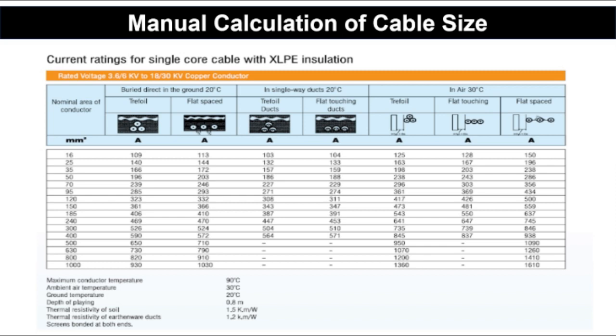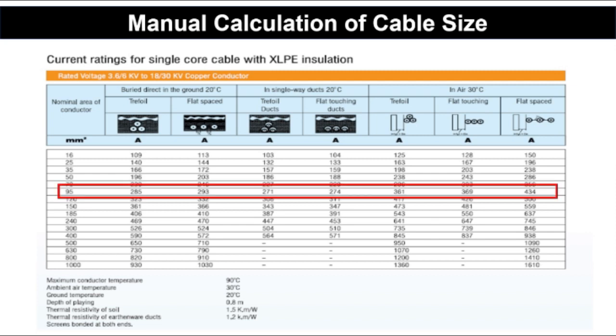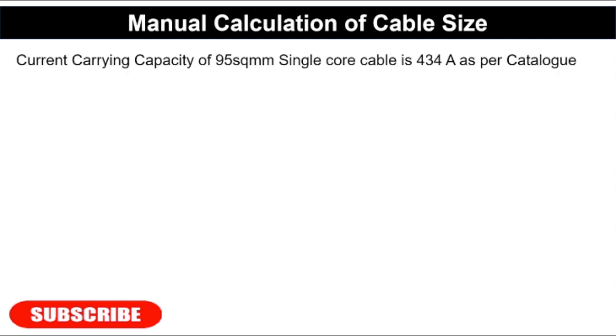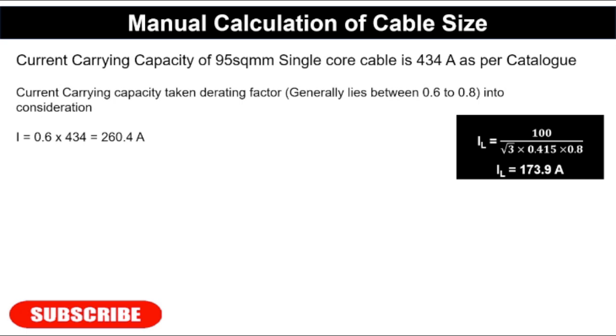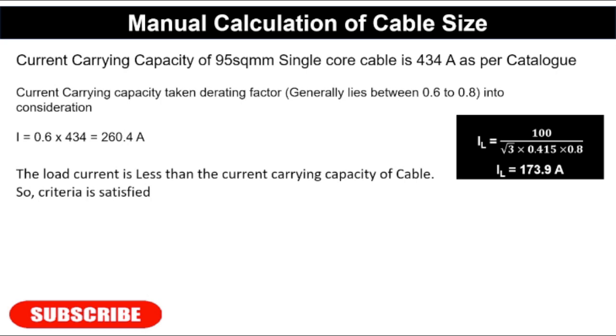Now we note the current rating of the 95 mm² cable from the catalog. The current carrying capacity of the 95 mm² single-core cable is 434 amperes in air at 30°C. Taking the derating factor of 0.6 into account, the derated current rating is: I = 0.6 × 434 = 260.4 amperes. Our load current is 173.9 amperes, which is less than 260.4 amperes, so the current carrying capacity criterion is satisfied.